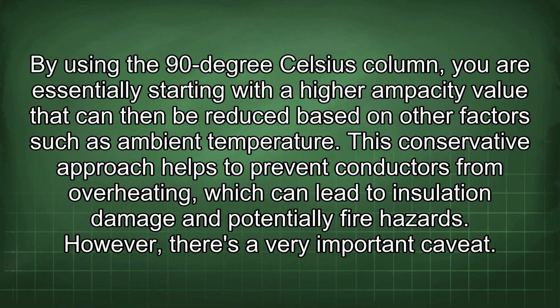By using the 90°C column, you are essentially starting with a higher ampacity value that can then be reduced based on other factors such as ambient temperature. This conservative approach helps to prevent conductors from overheating, which can lead to insulation damage and potentially fire hazards.